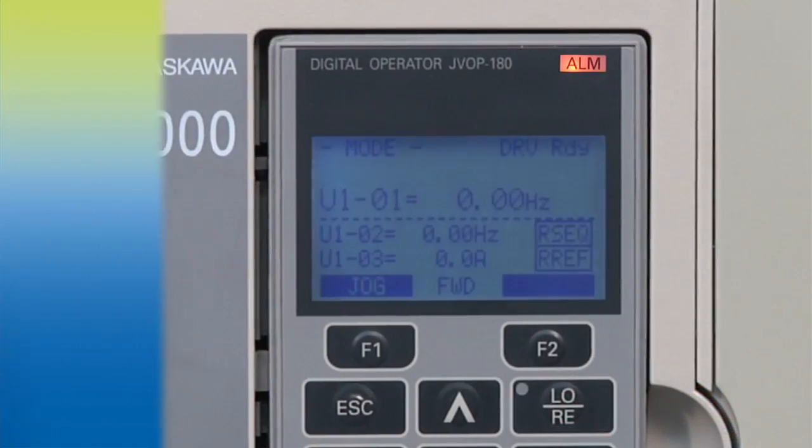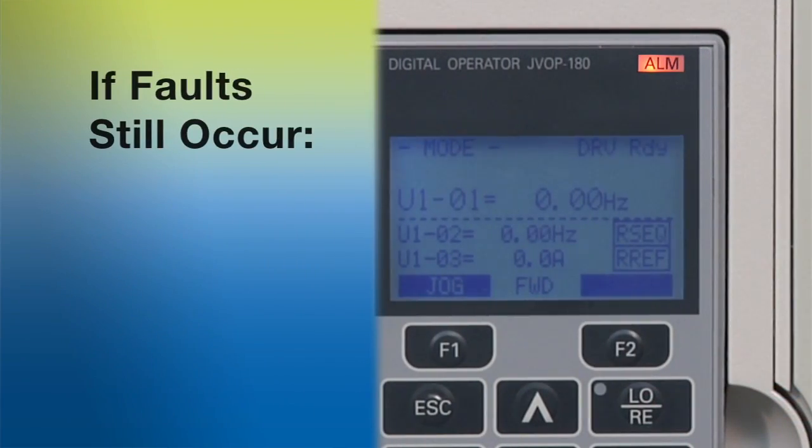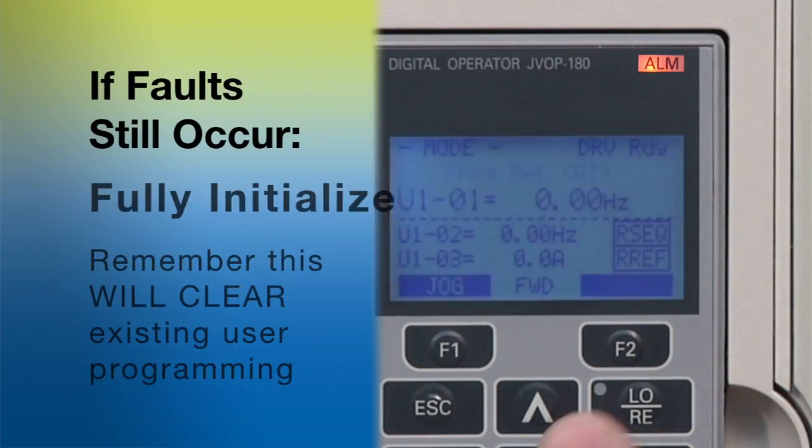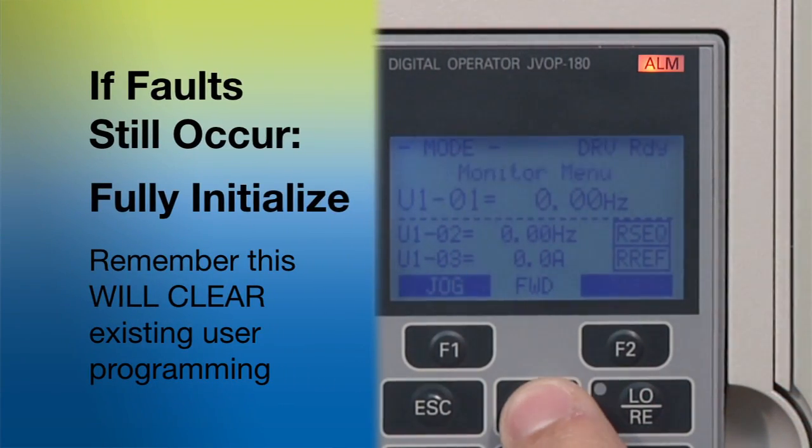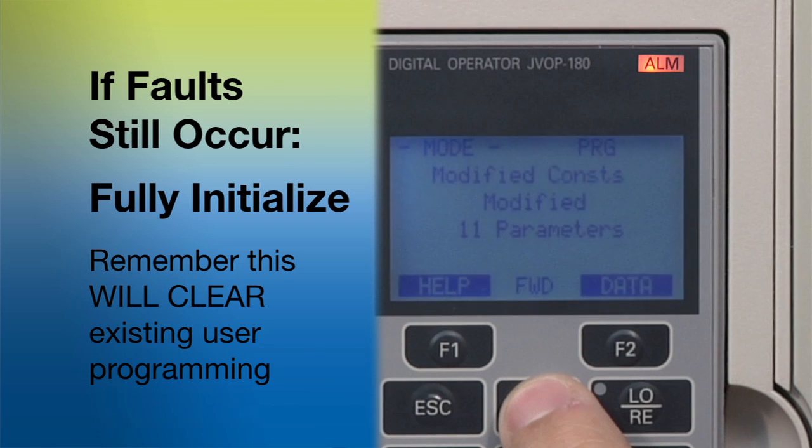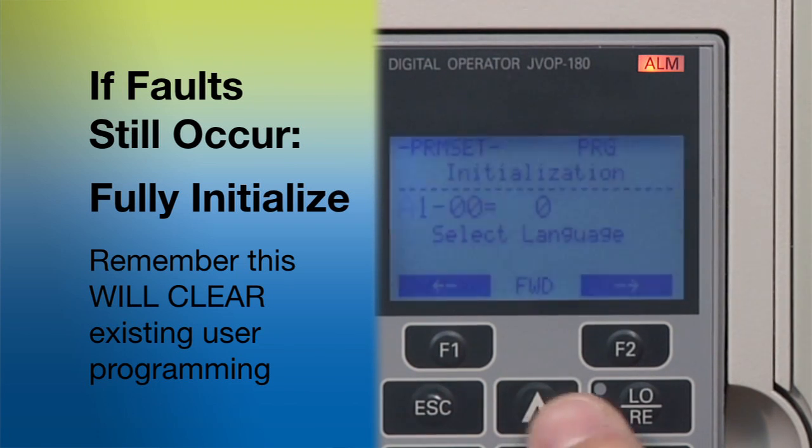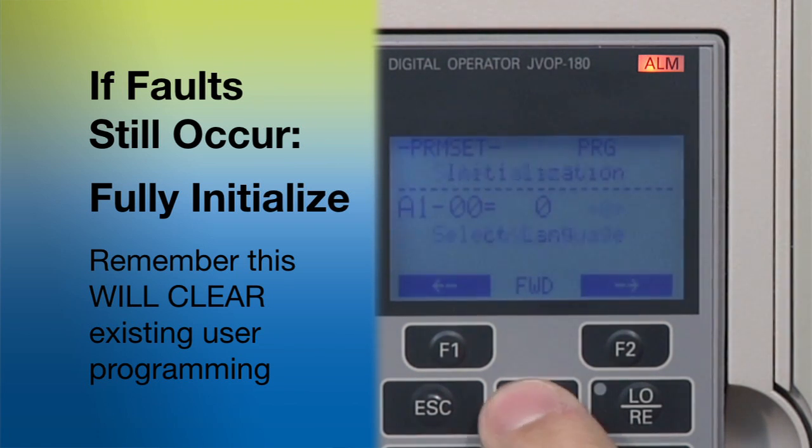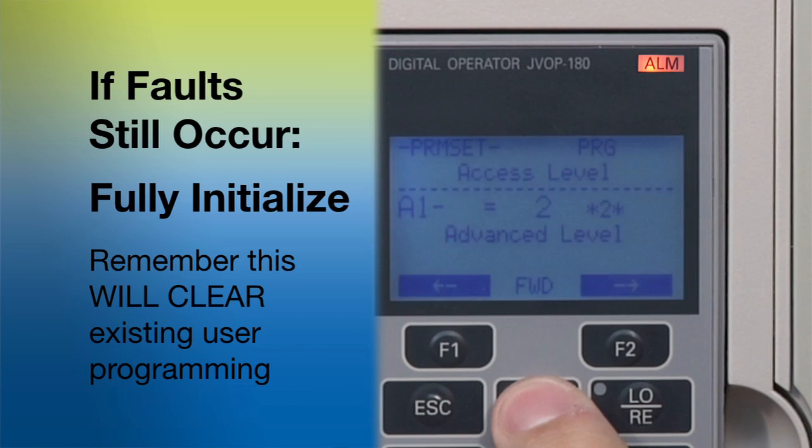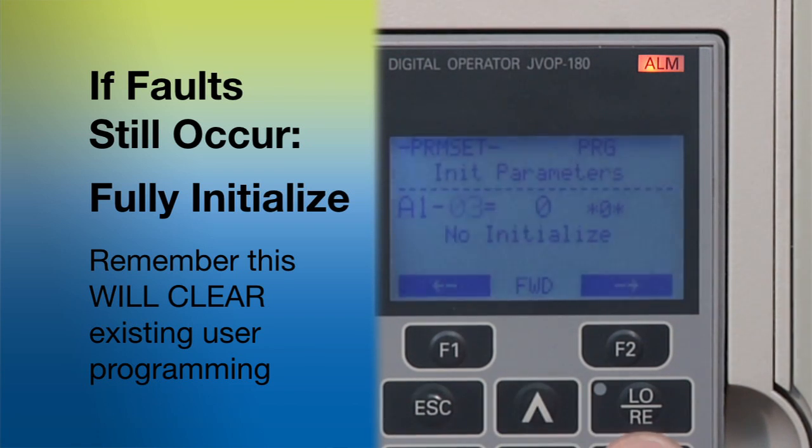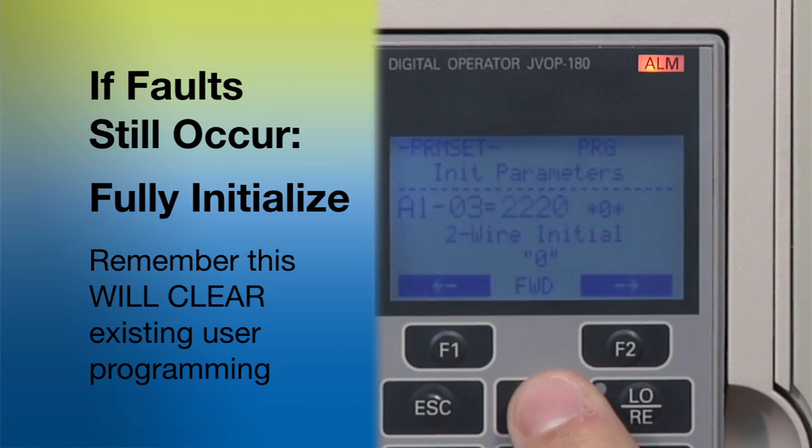If you're still getting alarms or faults, try reinitializing the drive. And before you do, remember that reinitializing will clear out the drive's current programming. On the other hand, reinitializing the drive should remove most alarms and faults.